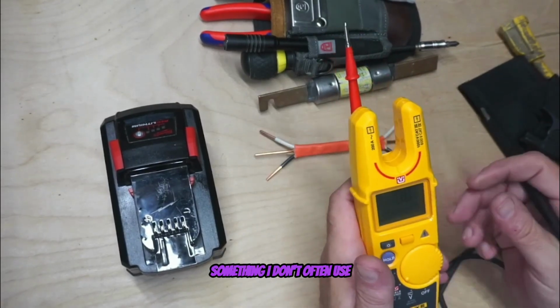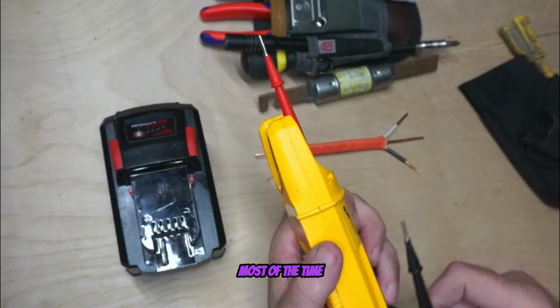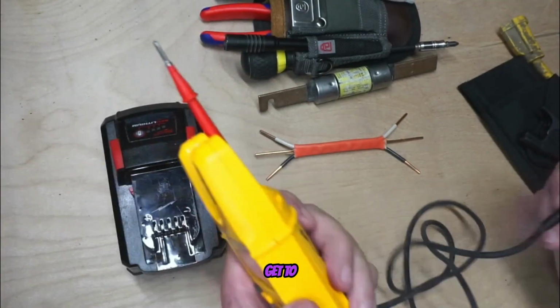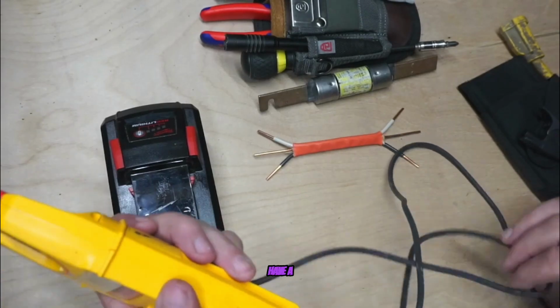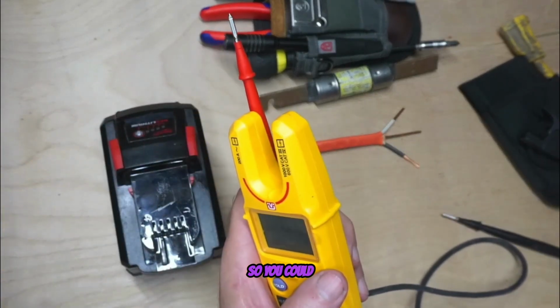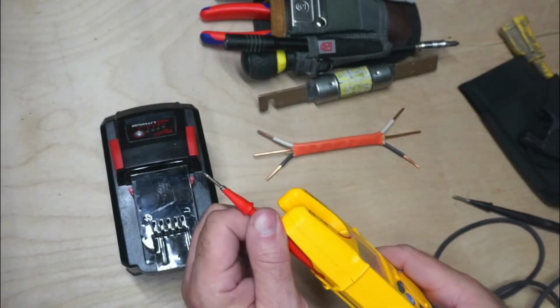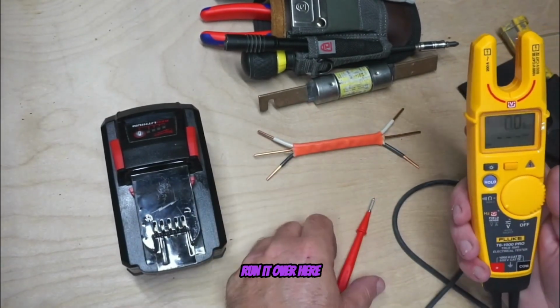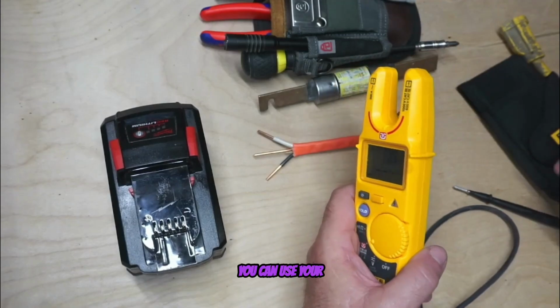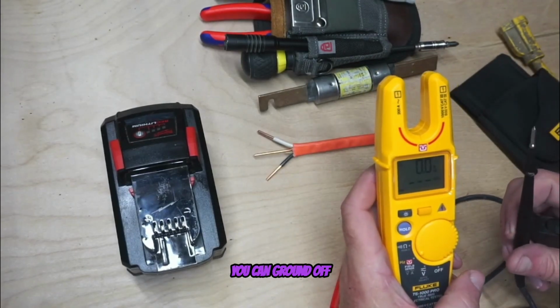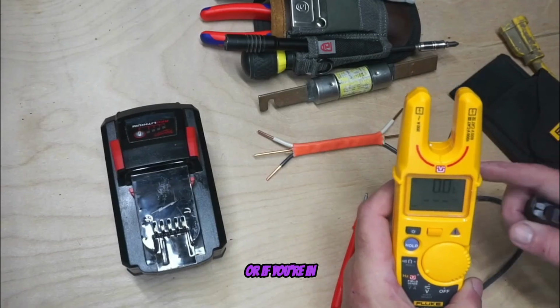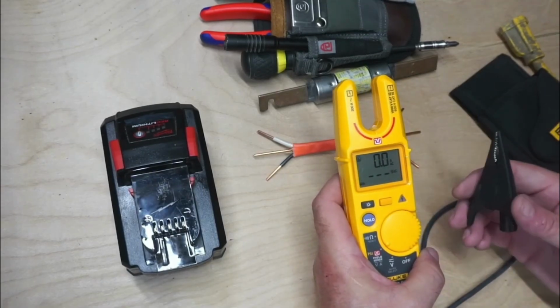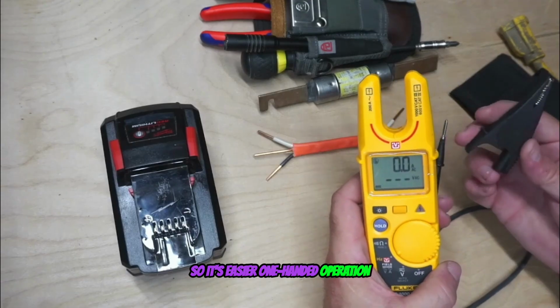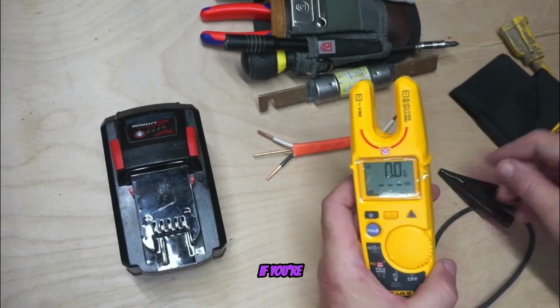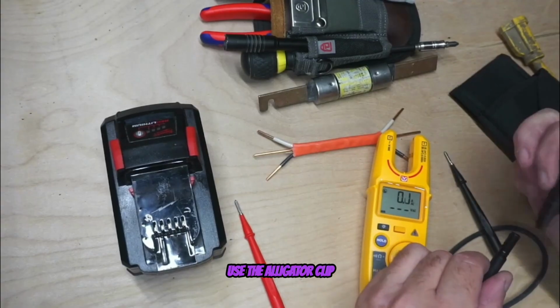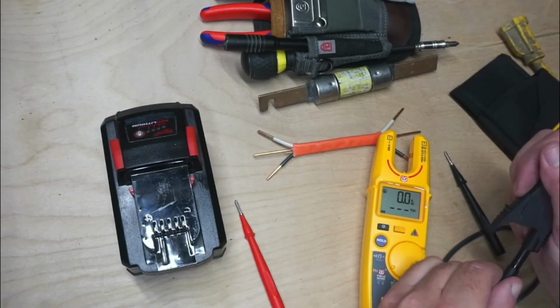The field sense is something I don't often use. Most of the time we have good connections everywhere we can get to, but I can see where you'd have a long run of wire without a good break in it, so you could get your probe in there to test it. In that case, you'd run it over to your field sense. You can use a ground-off point, like the conduit, or if you're in the electrical box, just run it on the ground side. You can clip it on here for easier one-handed operation, or use the probe if you're able to, using the alligator clip like that.